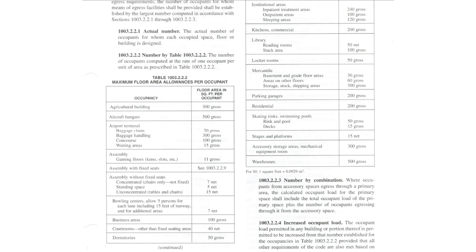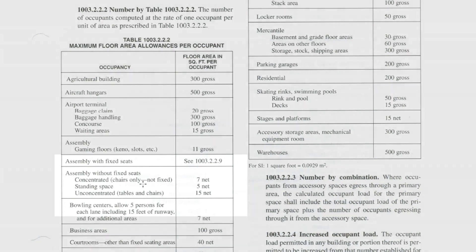The general guidelines for floor area allowances per occupant for A2 assembly are as follows: concentrated chairs only, not fixed, is 7 square feet per patron; standing space only is 5 square feet; and unconcentrated tables and chairs is 15 square feet.